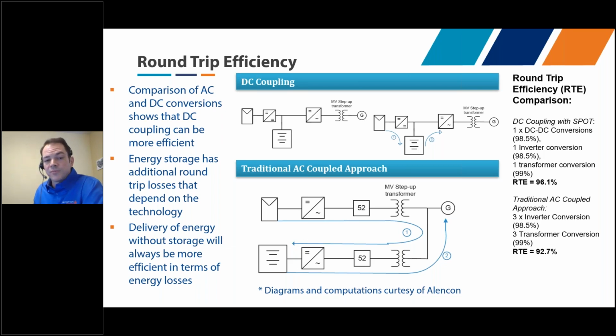The lower example is a traditional AC coupled approach: you go through solar panels, a DC to AC converter, potentially through a pair of transformers, then back through AC to DC conversion into the battery. There are obviously more conversions here, resulting in a net lower efficiency - down to a round trip efficiency more like 93%. The net of this is that delivery of energy through storage will always be more efficient in a DC coupled solution, and that's what we wanted to show here.